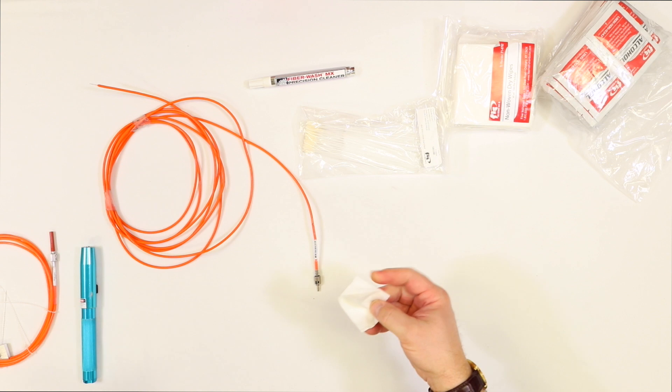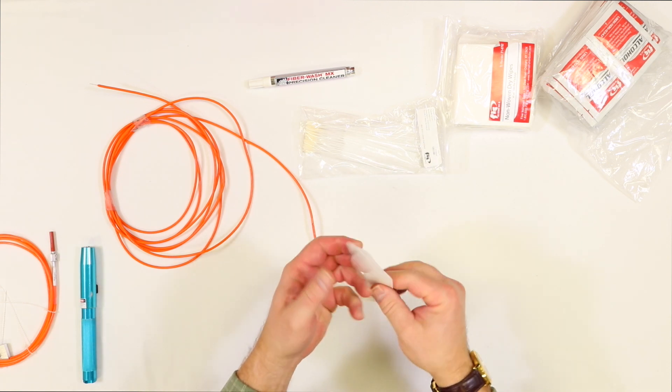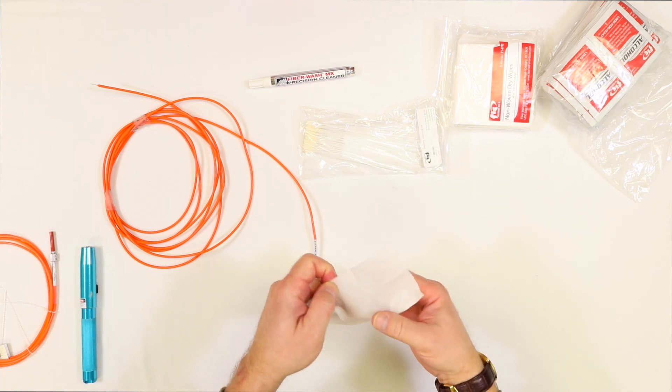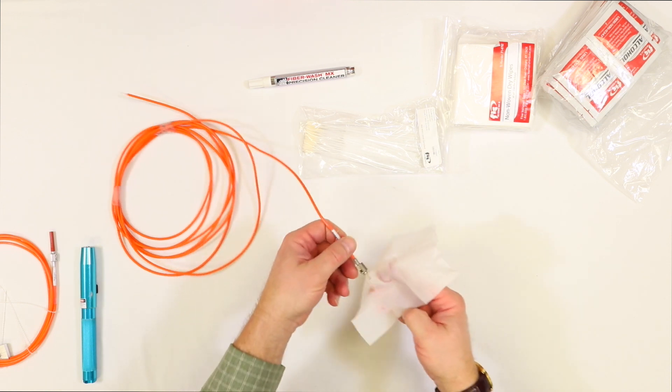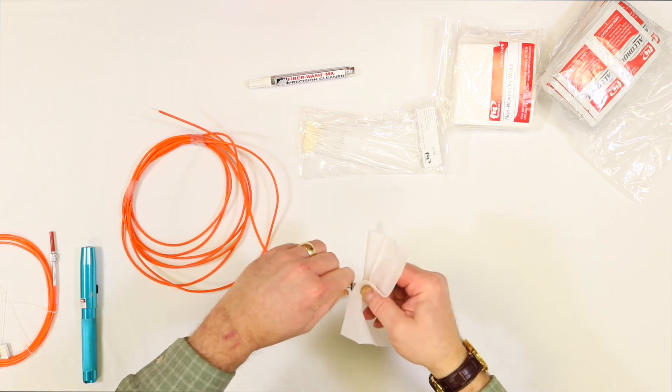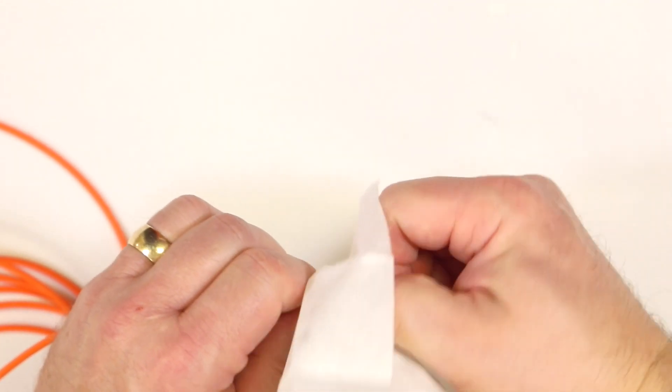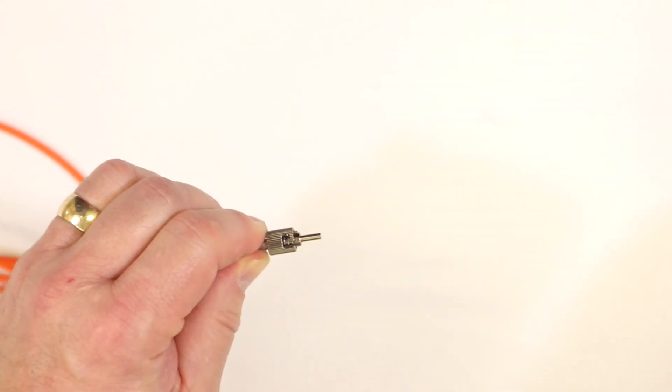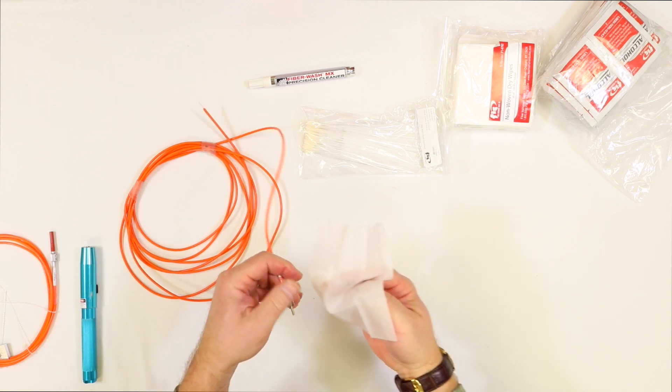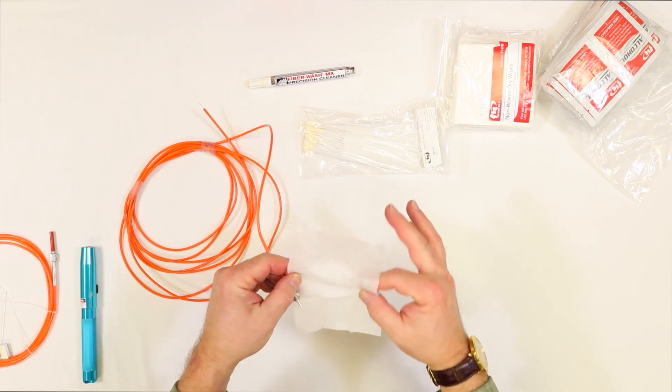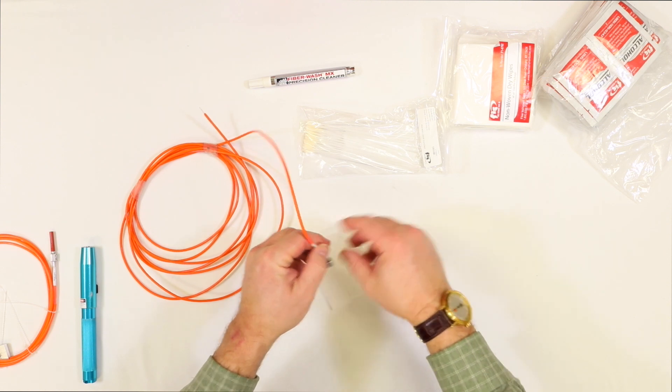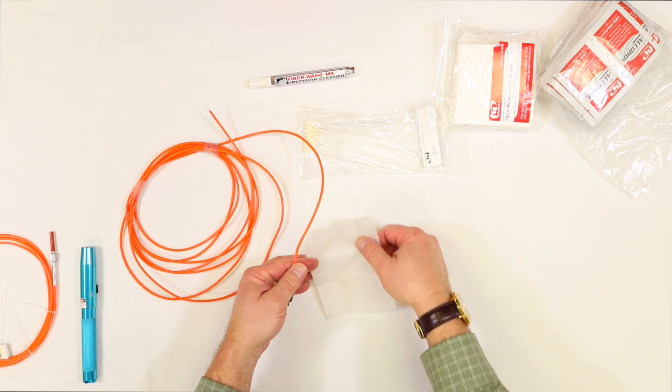There's a specific way to do that so you don't leave residue on the probe tip. Open up our wipe, wipe this around the ferrule one direction, and the last time we pull away from the point cleanly so that we take everything right off. You can see we've removed some junk from that.